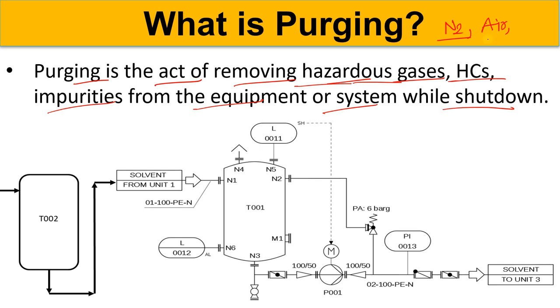The question arises: why is nitrogen most commonly used for purging? The main reason is that nitrogen is dry and it also acts as an inert gas. It is a dry and non-combustible gas, and it also displaces your combustible gases. When it displaces them, the combustible atmosphere is eliminated. That's why we use nitrogen most of the time as a purging gas or purging medium.